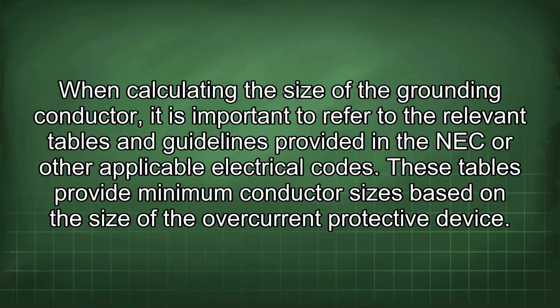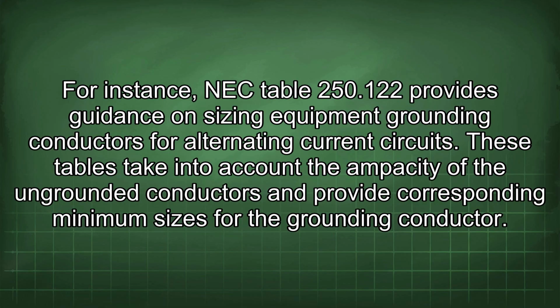When calculating the size of the grounding conductor, it is important to refer to the relevant tables and guidelines provided in the NEC or other applicable electrical codes. These tables provide minimum conductor sizes based on the size of the overcurrent protective device. For instance, NEC Table 250.122 provides guidance on sizing equipment grounding conductors for alternating current circuits. These tables take into account the ampacity of the ungrounded conductors and provide corresponding minimum sizes for the grounding conductor.